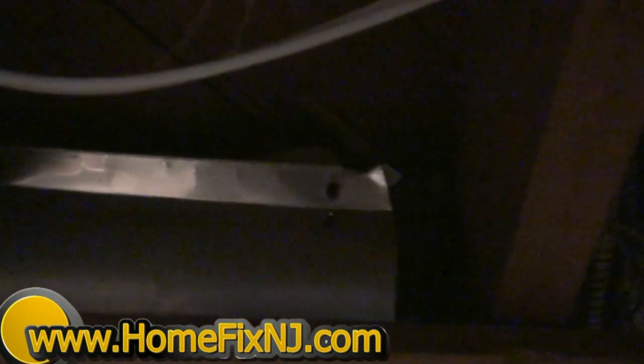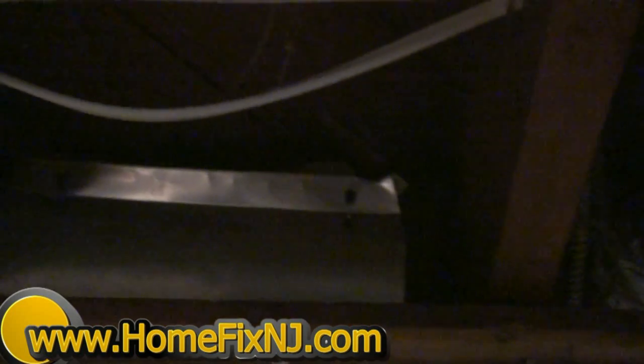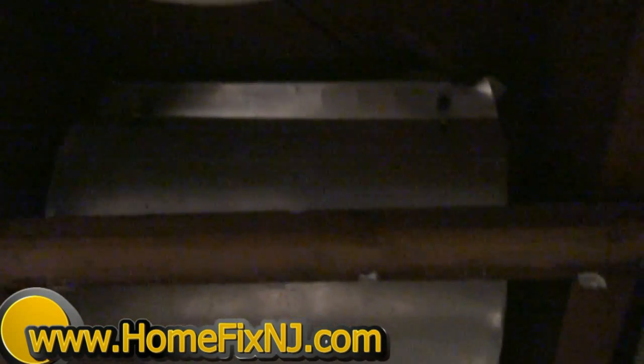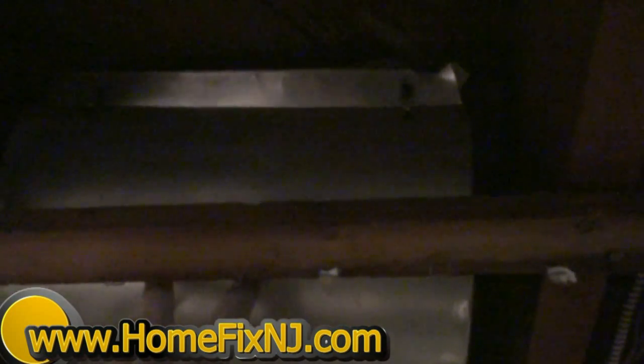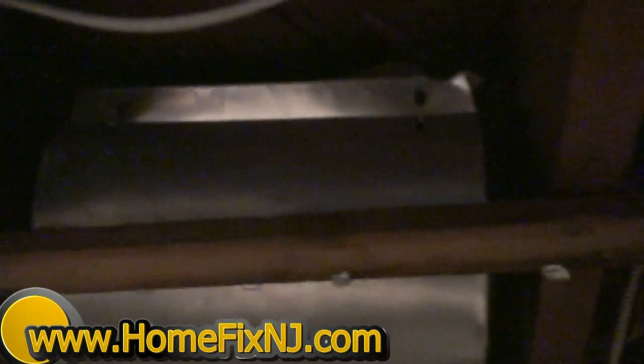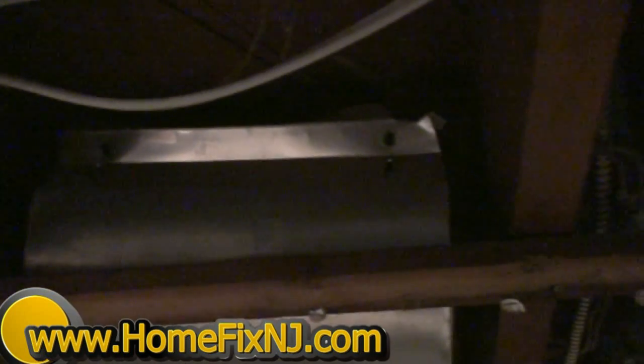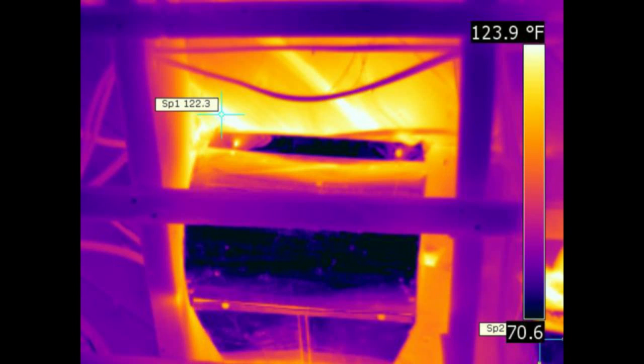The other thing we found was a floor register for another vent had just been removed, and the vent had just been left in there, basically blowing up against the bottom of the floor in the basement. So these were two big, wide open registers in the basement that weren't necessary to heat unconditioned space. Here's a picture of what the removed floor register looked like when we put the thermal imaging camera on it. You can see a lot of heat just blasting against the floor and basically going nowhere, staying in the basement.